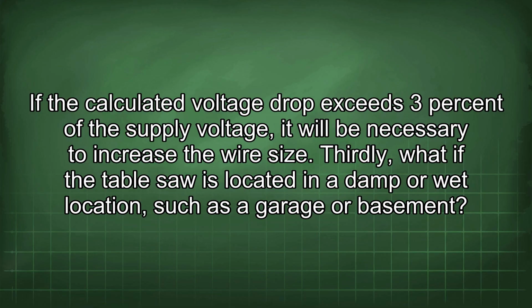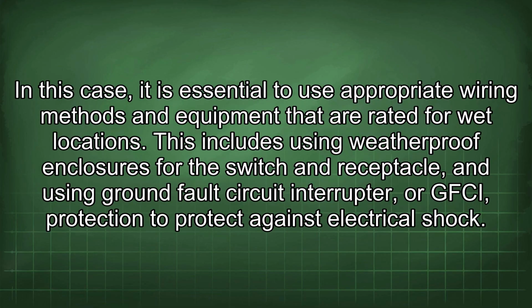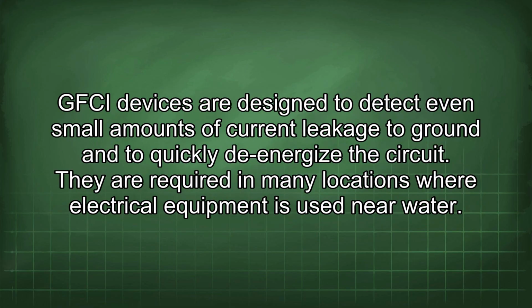Thirdly, what if the table saw is located in a damp or wet location, such as a garage or basement? In this case, it is essential to use appropriate wiring methods and equipment that are rated for wet locations. This includes using weatherproof enclosures for the switch and receptacle, and using ground fault circuit interrupter, or GFCI, protection to protect against electrical shock. GFCI devices are designed to detect even small amounts of current leakage to ground and to quickly de-energize the circuit. They are required in many locations where electrical equipment is used near water.